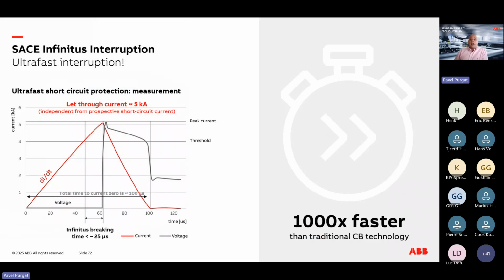When we look at the actual measurement, so how it looks when this device operates, it's very similar to the theoretical picture that we've seen. The worst breaking time is 25 microseconds. It's also given a little bit by the system inductance. That's why it's a bit higher, but on average, it's below 20 microseconds. And because of that, the let-through current of this device is pretty much defined. Let-through current is usually around 5 kiloamperes, but never more than 6. And this, you can imagine, is quite a difference when we have a fuse or an electromechanical device, where we are never quite so precise with these let-through currents.